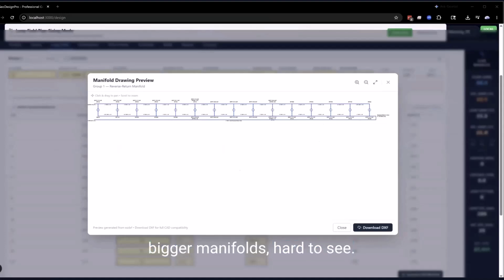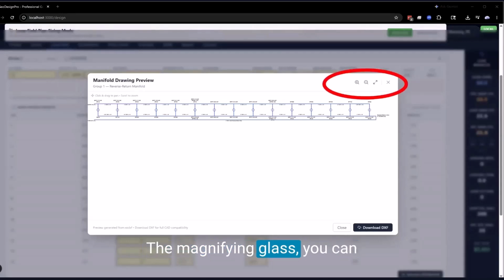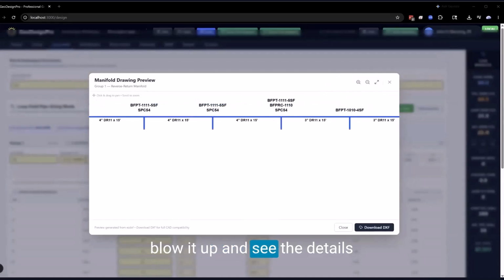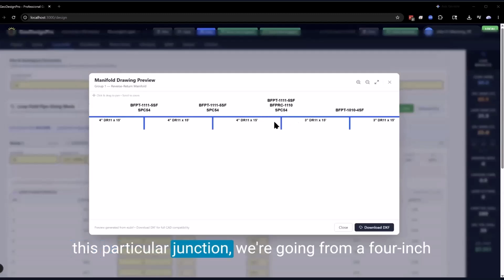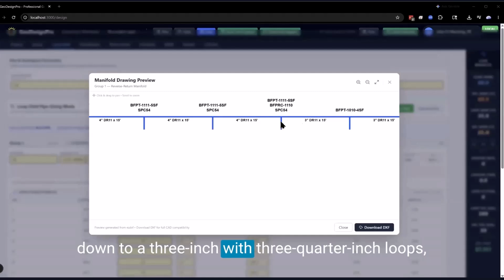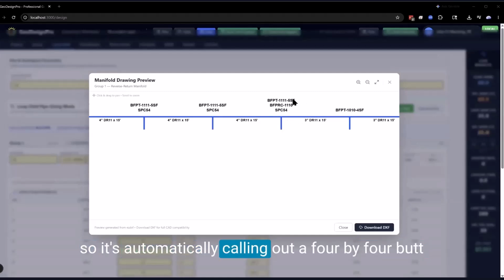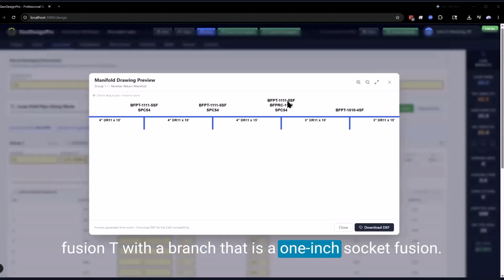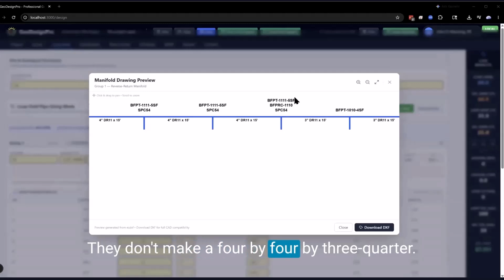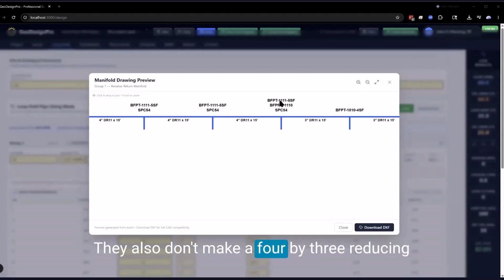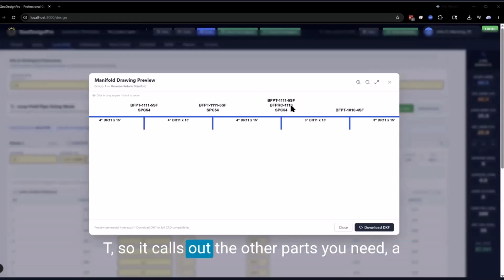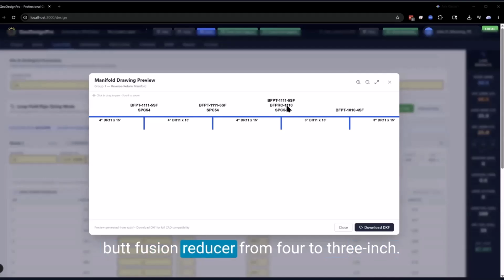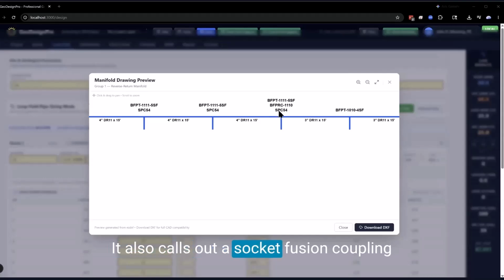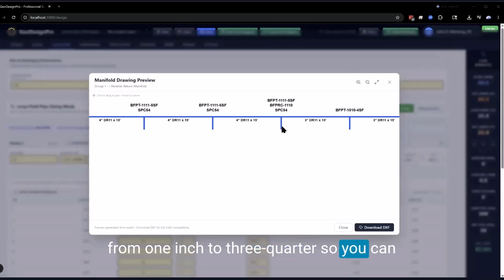But then you can have much bigger manifolds, hard to see. We've got tools at the top, the magnifying glass. You can blow it up and see the details. In this particular junction, we're going from a 4-inch down to a 3-inch with 3/4-inch loops. So it's automatically calling out a 4x4 butt fusion T with a branch that is a 1-inch socket fusion. They don't make a 4x4 by 3/4, and they also don't make a 4x3 reducing T. So it calls out the other parts you need: a butt fusion reducer from 4 to 3-inch, and a socket fusion coupling from 1-inch to 3/4 so you can reduce down and connect to the loop.